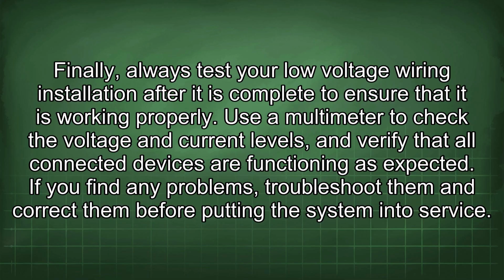Finally, always test your low voltage wiring installation after it is complete to ensure that it is working properly. Use a multimeter to check the voltage and current levels and verify that all connected devices are functioning as expected. If you find any problems, troubleshoot them and correct them before putting the system into service.